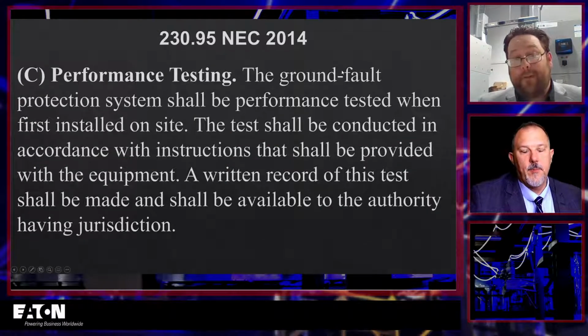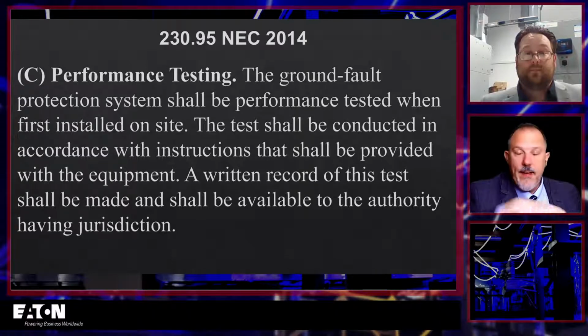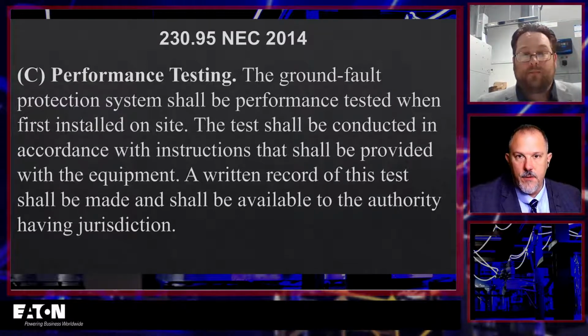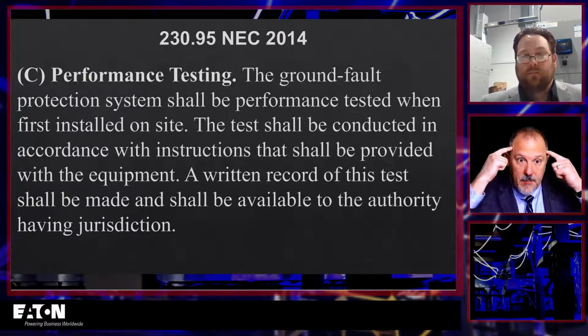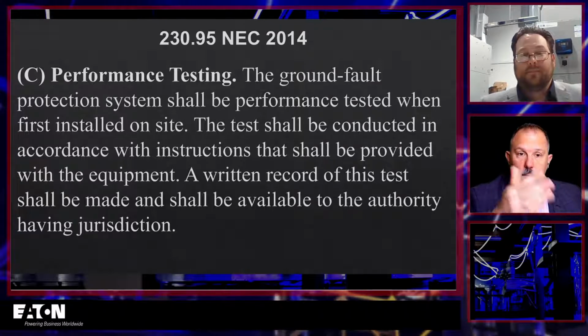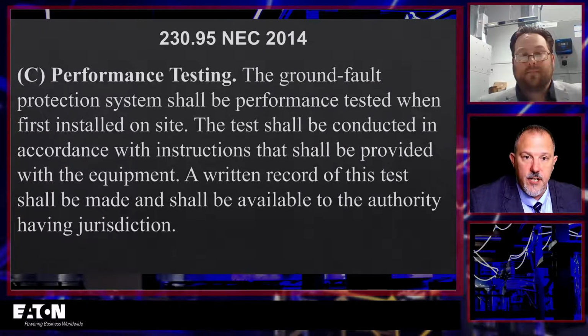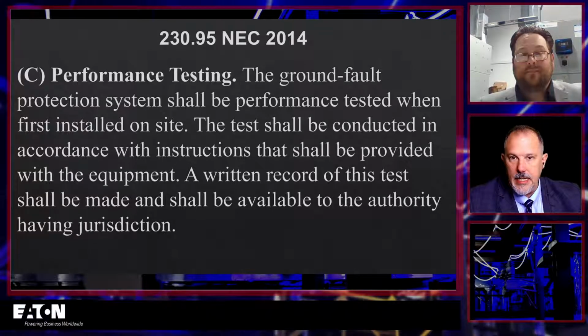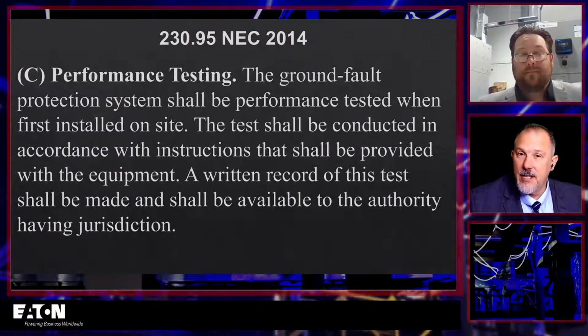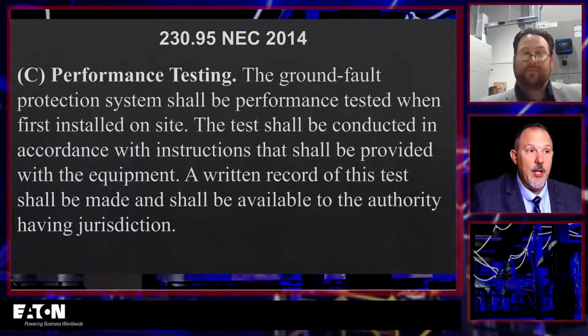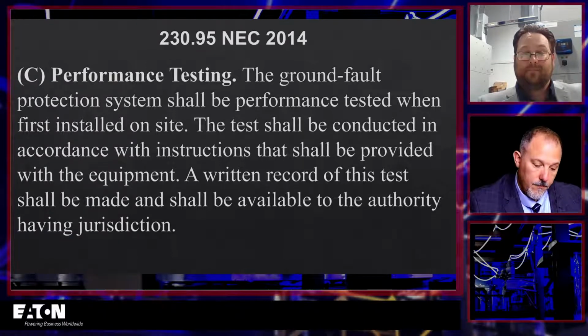Absolutely. And from a performance testing perspective, we had this discussion, and you'll notice that 240.87 and 240.67 in the National Electrical Code this 2020 cycle included performance testing of those solutions. I think we have to keep that in mind, because what we're talking about is performance testing on installation of ground fault protection of equipment at 1,000 amps and above. And if you're at 1,200 amps and more, then you have both GFPE performance testing and arc reduction technology performance testing. And sometimes you can kill both with one stone. And you have to make sure you plan it correctly.